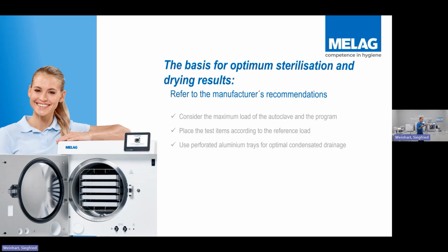So it is important that we do refer to the manufacturers of the autoclaves that you have to ensure that we are loading that autoclave correctly. Okay, that's the important part. Using a perforated aluminium tray is the optimum benefit in terms of ensuring that we get no condensates on there. So what you'll notice with most perforated aluminium trays is you've got multiple evenly spaced holes throughout the tray. And then you should also have drainage holes at the end of each corner just to allow the water that is condensed on there to drain out, and it helps to condense out.